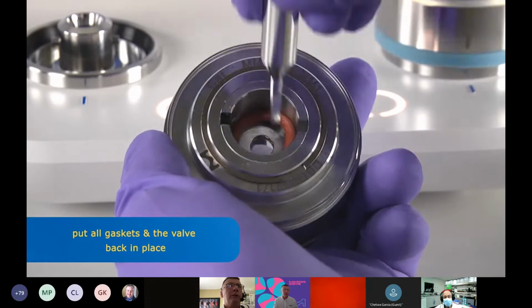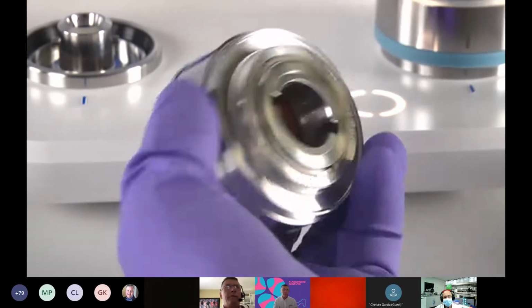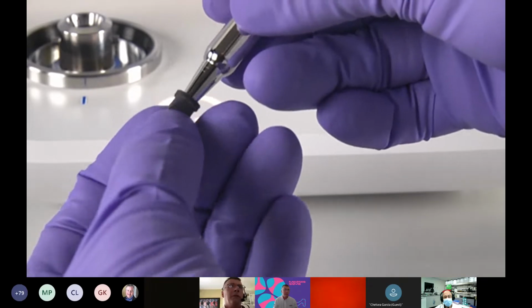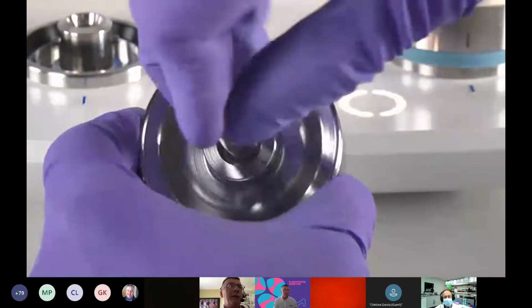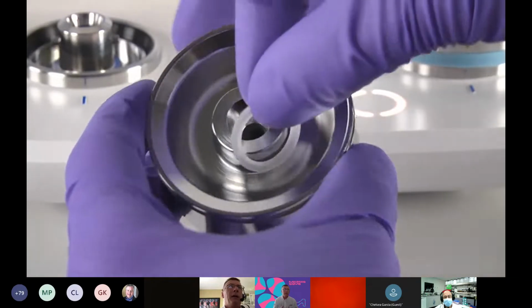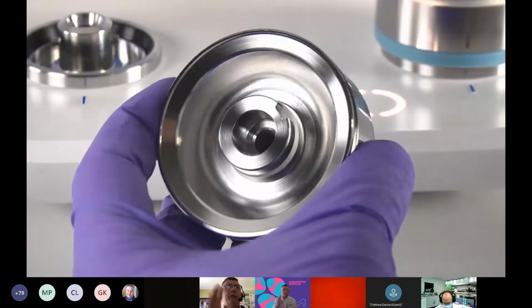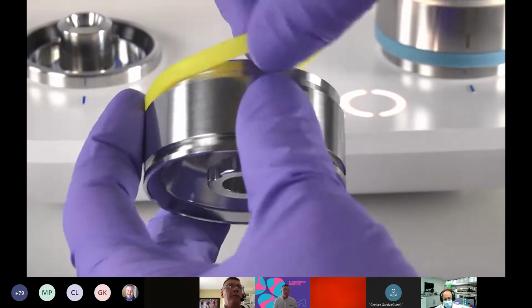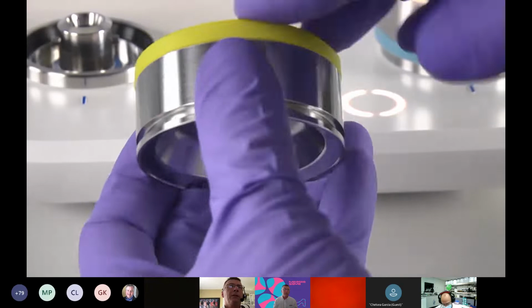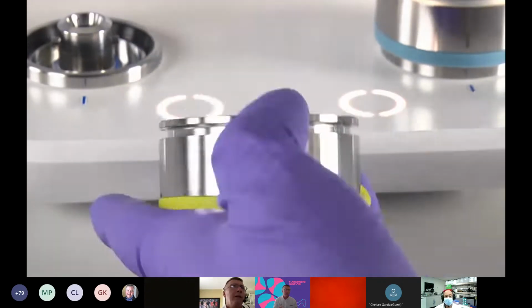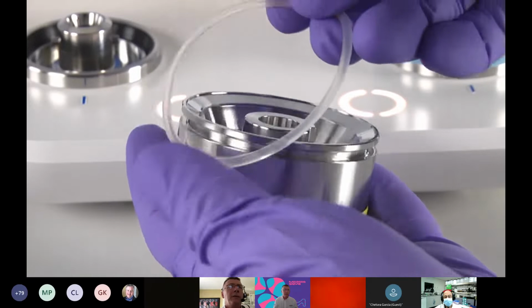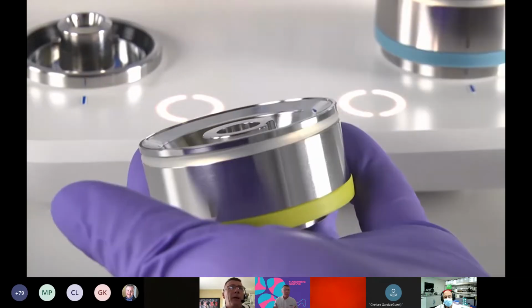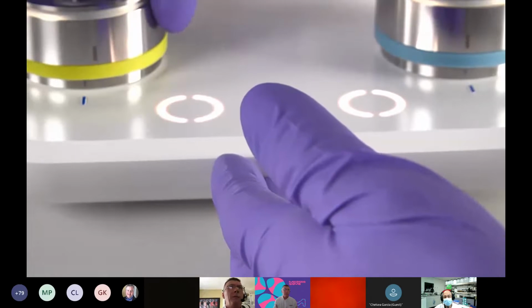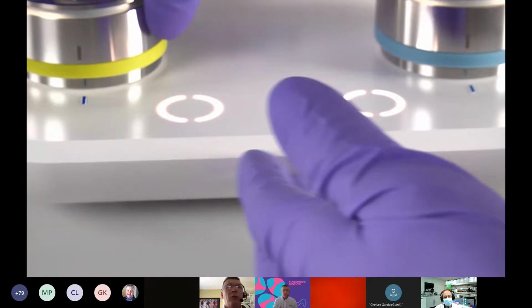So after you clean your unit, you just put the O-rings back in. It's very simple, and you can see that the process doesn't take much time. This little tool that you see them using comes as part of the pump, and you could buy the kit, which comes complete with all of these bands and O-rings that allow you to change and identify your pump head. So with that, you just add the last O-ring and you'd be ready to go. You could see that within the span of 15-20 minutes, your pump would be completely sanitized and ready to go for the next month. A very, very simple process in comparison to what is currently being done.